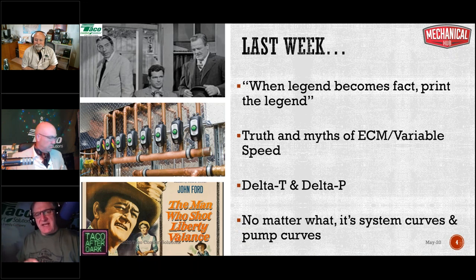And here's maybe the big takeaway from last week, and to me it cuts to the very essence of how hydronics works. The circulator may very well be the most important component in the system in determining how effectively, how efficiently, how economically, and for how long that system is going to operate in a relatively trouble-free manner. The circulator's the thing that makes the water go round and round. The boiler makes the heat, and that's important, but the heat's just sitting in the boiler unless something happens. The heat emitters deliver the heat, but they're just sitting there in the room waiting for the heat to get from the boiler to them. The circulator facilitates that journey, and how it does it and in what manner is going to make a huge difference in how your system operates.